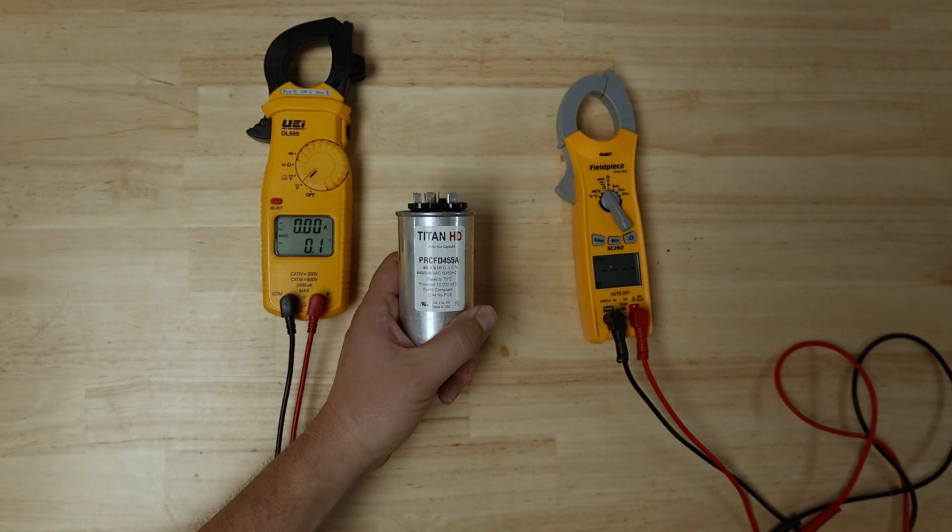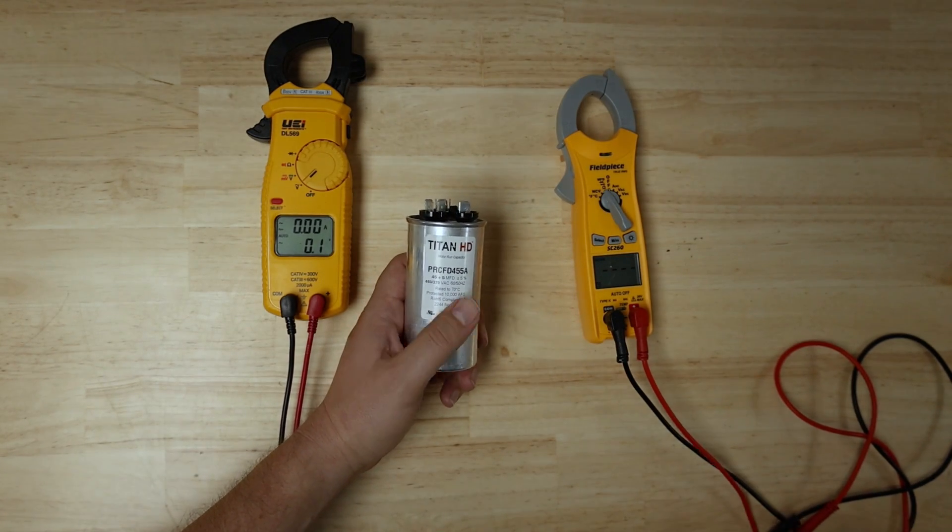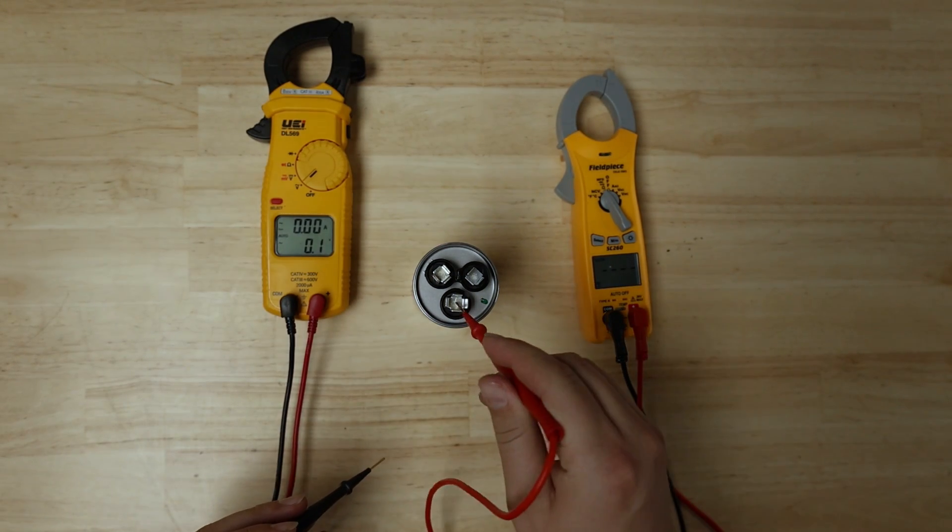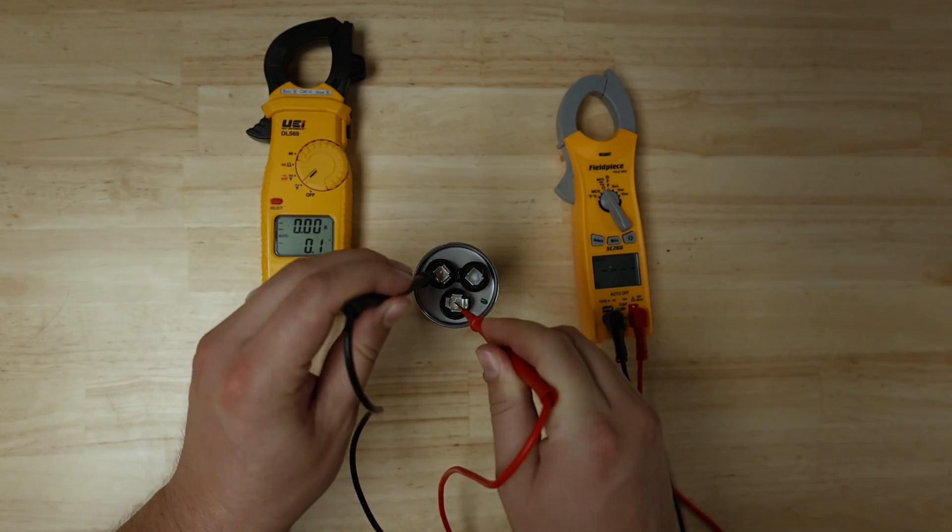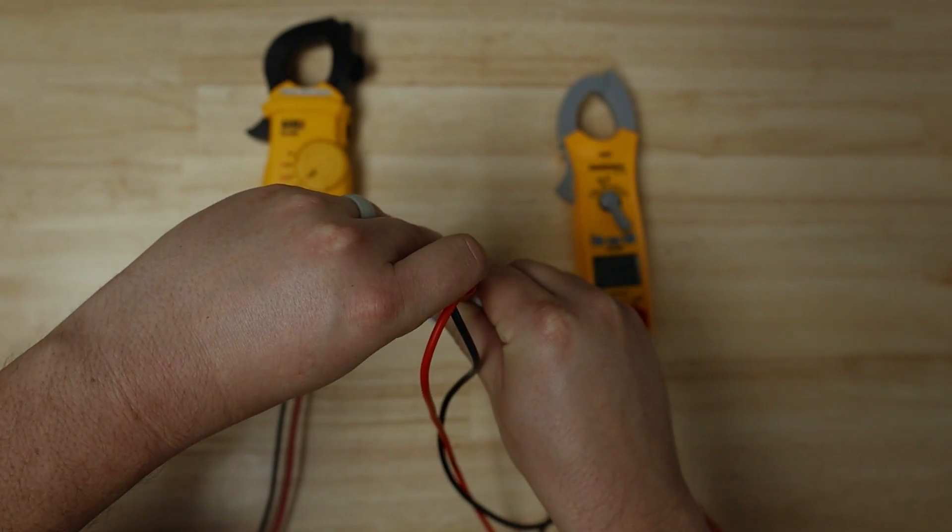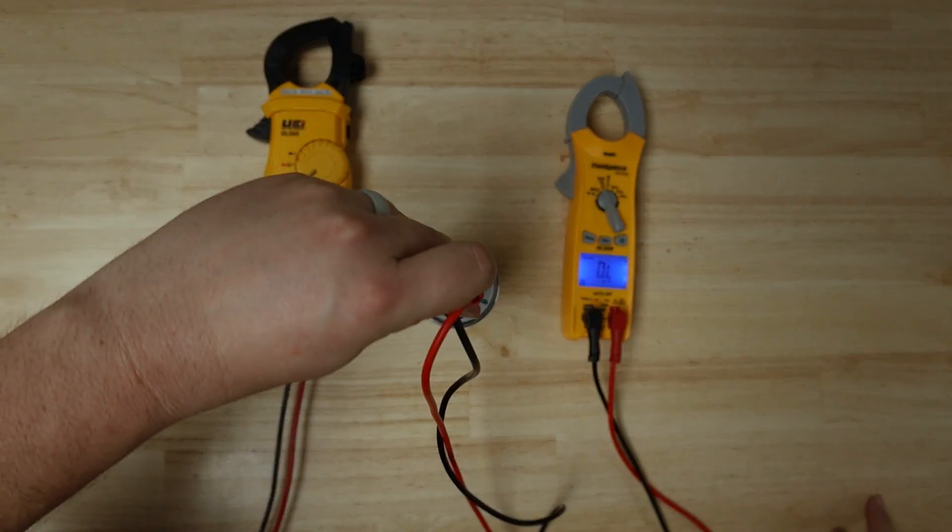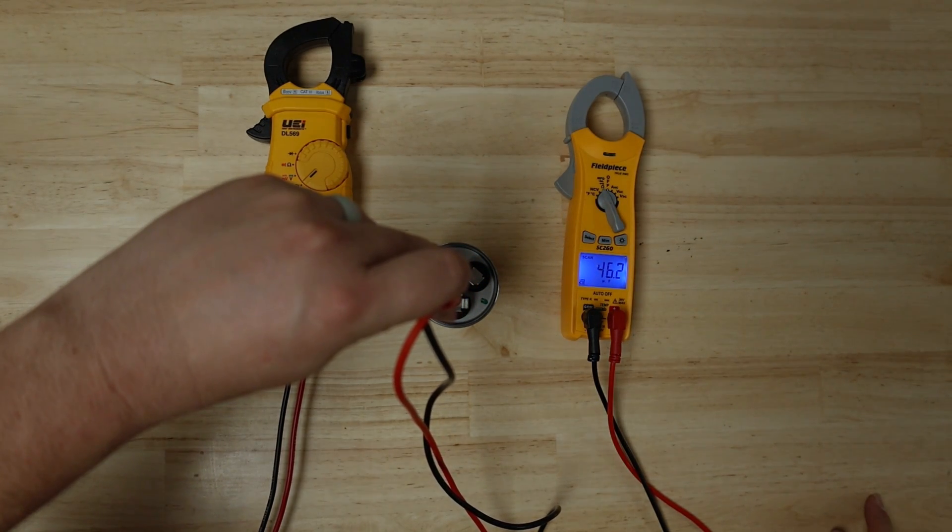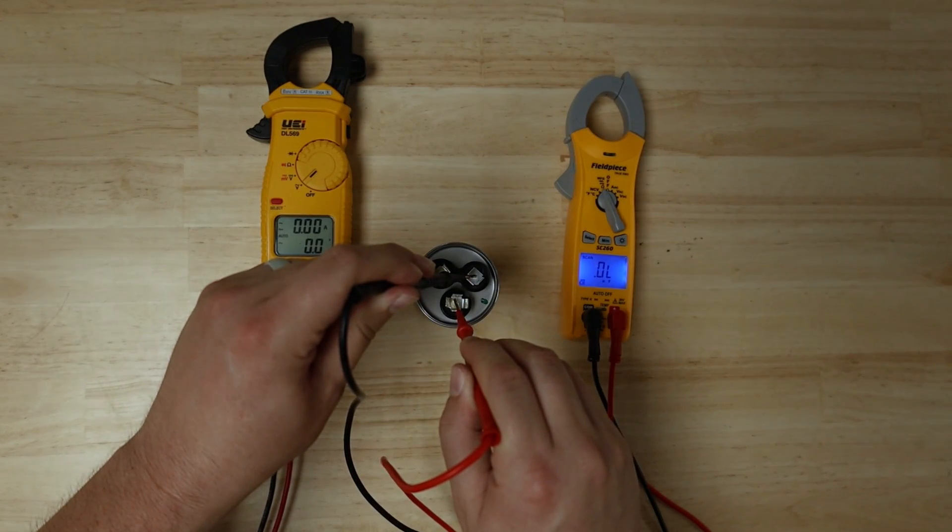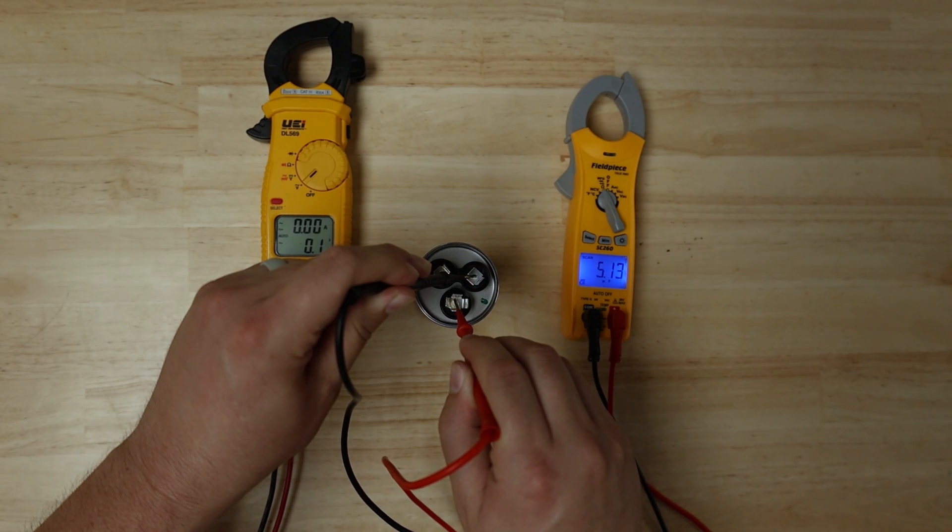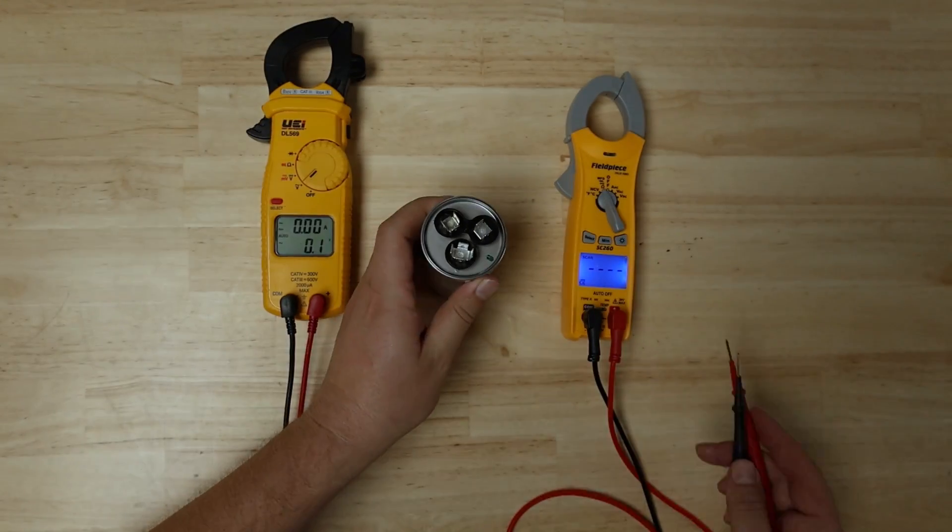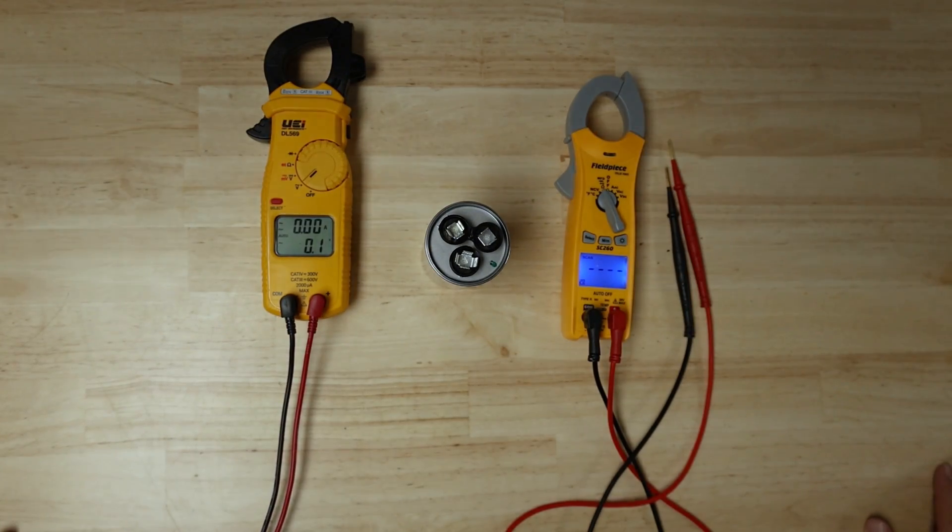Here we have a 45 by 5 dual capacitor, so it'll have both fan and compressor on it. We're going to measure between the common and the hermetic first. Our number will be 46, so we're good on the compressor side. Now we'll measure between the common and the fan side, and there we'll see 5 microfarads. So this capacitor is reading well, and that's how you measure microfarads with the Fieldpiece meter.